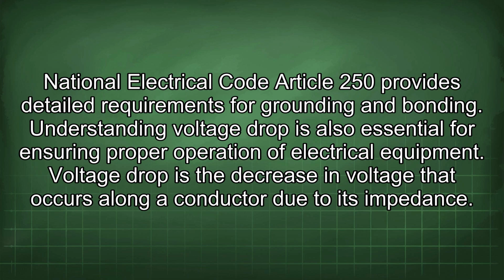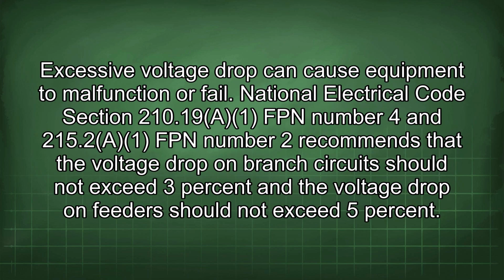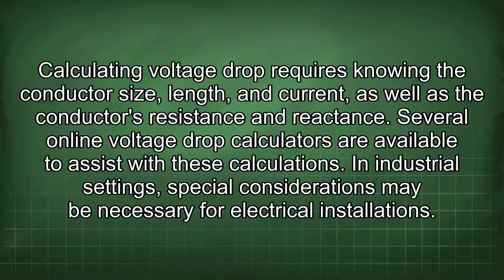Understanding voltage drop is also essential for ensuring proper operation of electrical equipment. Voltage drop is the decrease in voltage that occurs along a conductor due to its impedance. Excessive voltage drop can cause equipment to malfunction or fail. National Electrical Code Section 210.19(A) Informational Note No. 4 and 215.2(A) Informational Note No. 2 recommend that the voltage drop on branch circuits should not exceed 3% and the voltage drop on feeders should not exceed 5%. Calculating voltage drop requires knowing the conductor size, length, and current, as well as the conductor's resistance and reactance. Several online voltage drop calculators are available to assist with these calculations. In industrial settings, special considerations may be necessary for electrical installation.